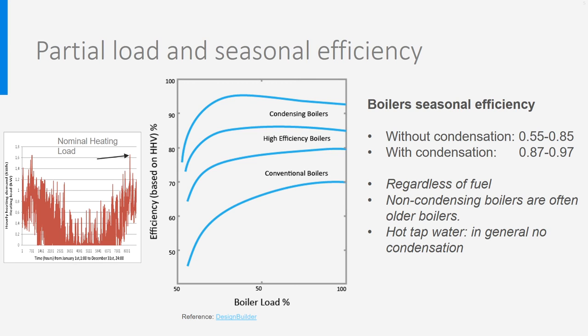Concerning boilers for hot tap water, condensing boilers are generally not applicable as the temperature should be kept above 60°C to avoid growth of legionella bacteria, which is harmful for human health. However, such a temperature is needed only once a week, which makes it possible to lower the temperature to 50°C and therefore profit a little from the condensation heat.